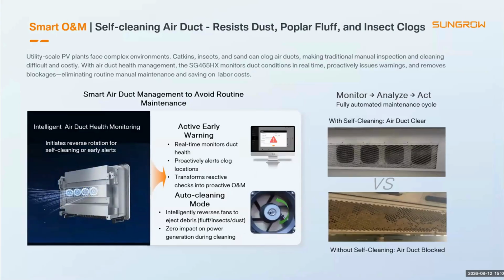So dust, sand, and insects can block cooling air ducts and increase maintenance work. Our inverter monitors air duct condition in real time. If blockage is detected, the fan can automatically reverse to remove debris. This turns routine manual inspection into a more intelligent, condition-based maintenance process.